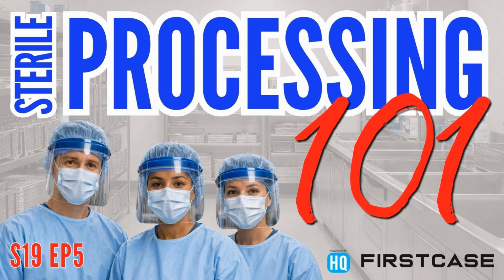So the majority of sterile processing departments out there in a hospital are going to have steam autoclaves. Steam is available in every facility because we use it for our boilers and hot water and all of that. So it's easily accessible, it's cheap, and it's wildly effective at sterilizing instruments. And so that's the lion's share, 80% of the instruments, I just made that number up, but 80% of the instruments that go through the department are going to go through a steam autoclave, and we can dive deeper into that. There are also some low-temp options out there because there might be some instruments that can't handle the hot, wet, high pressure conditions of a steam sterilizer.